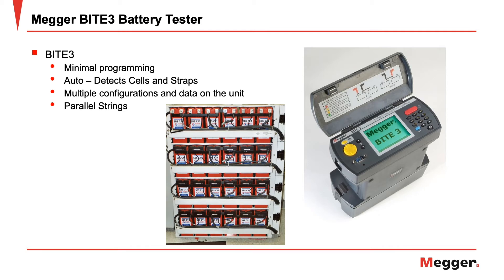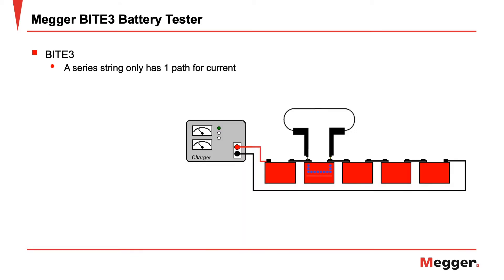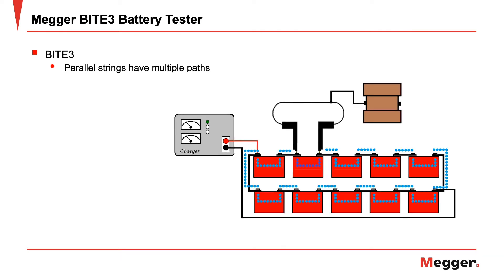The BITE3 can test parallel strings without any need to segment the strings. When testing a series string, the test current only has one path it flows through. In parallel strings, the test current will have multiple paths to flow through. As one cell's impedance changes, it changes the current flow through each string, which changes the measurement on all the cells, making locating the poor cell impossible.